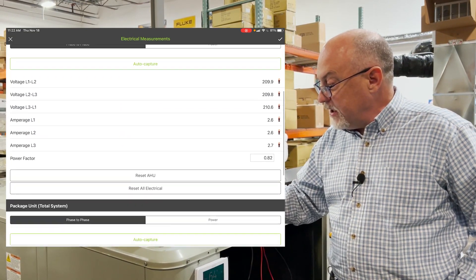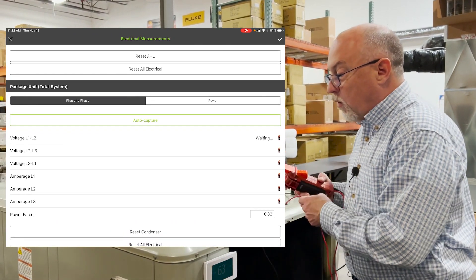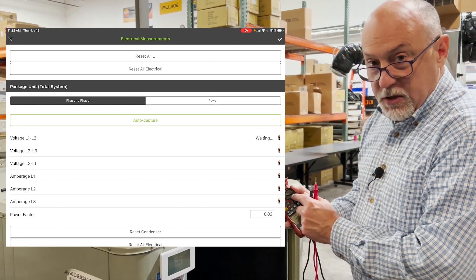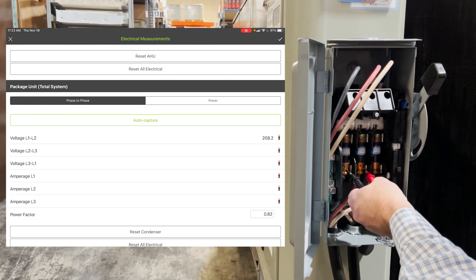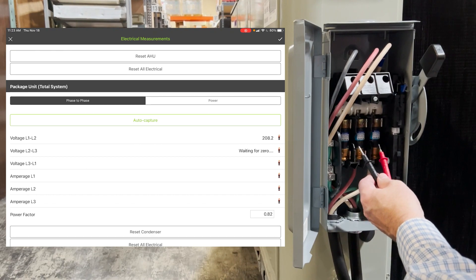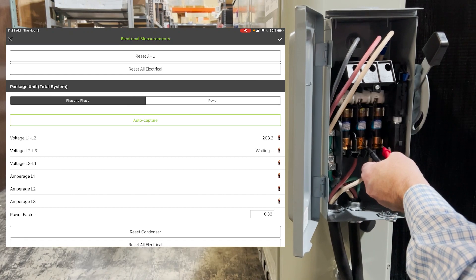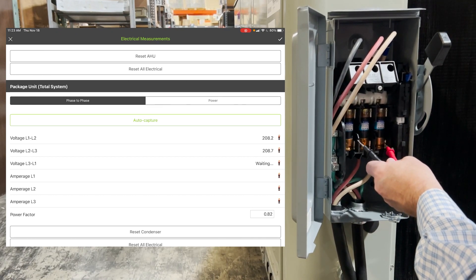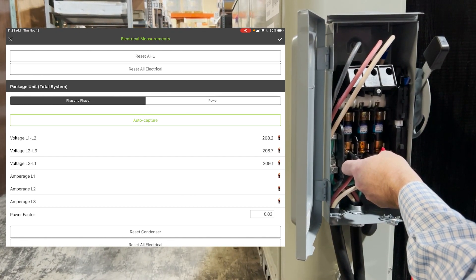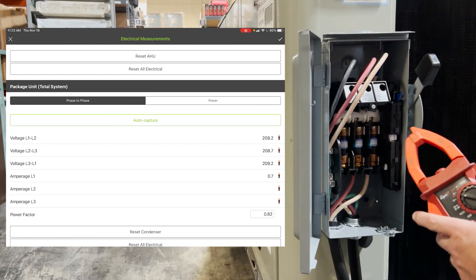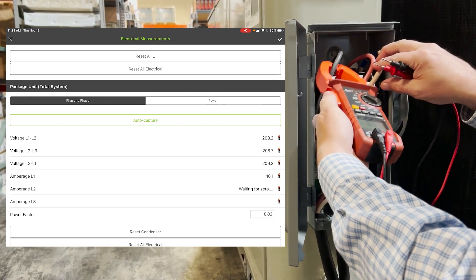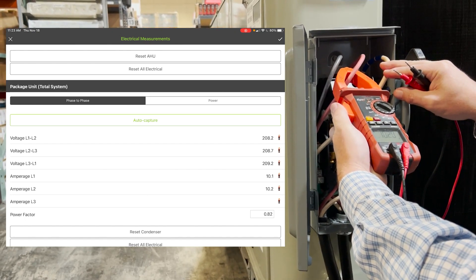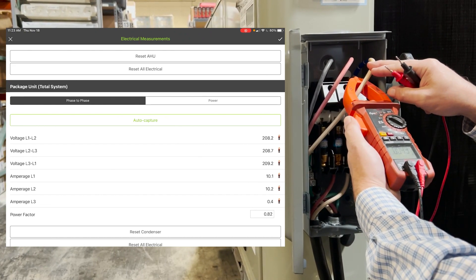So back in the electrical measurements section here, we'll scroll down a little bit. You see the auto capture's on because it says waiting here. So again, we're going to go to L1 to L2. We'll get the voltage on the condenser. So I have to make sure I have the meter set to voltage here. We'll go ahead and get L1 to L2. Again, you're going to hear a double tone, a triple tone. So that's telling us it's captured. We'll pull it off. We got it. We'll do L2 to L3. Pull it off, and then L3 to L1. Got it. Now we're just going to switch the meter to amps. Go across. Got it. Go back to zero. Back on. Back to zero. And back on L3.